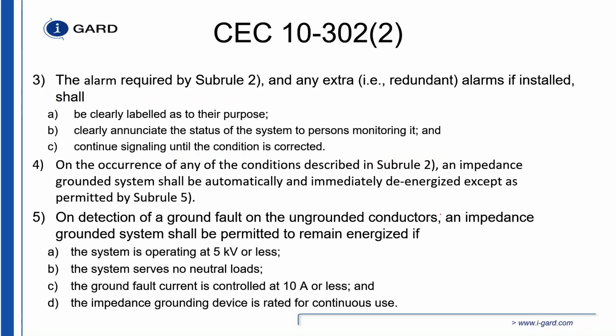On detection of a ground fault on an ungrounded conductor, the impedance grounded system shall be permitted to remain energized if you're operating at 5 kV or less, you serve no line to neutral loads, you limit the ground fault current to 10 amps or less, and the impedance grounding device is rated for continuous use. This is low voltage, right? Anything up to 600 volts. So if you have line to neutral loads, you must trip. If you limit the fault current to more than 10 amps, you must trip. If you're greater than 5 kV, you must trip. If you have a resistor that's rated for 10 seconds, 60 seconds, extended duty, you must trip. But if you comply with 5 kV or less, you have no line to neutral loads, or you don't have a distributed neutral, 10 amps or less, and you have a continuous rated resistor, you don't have to trip.